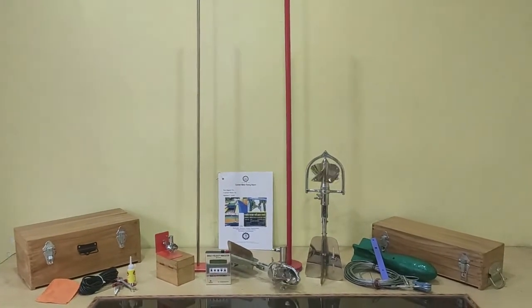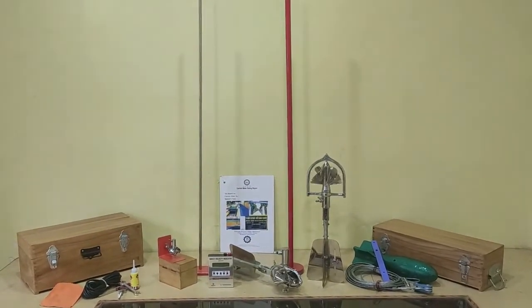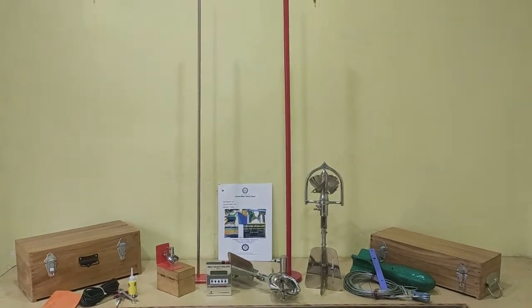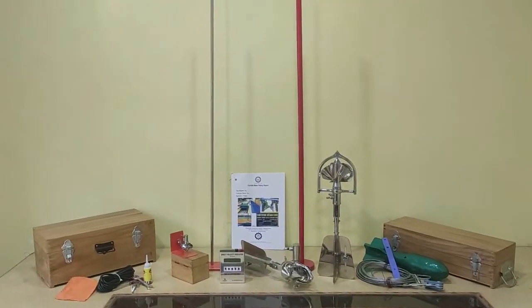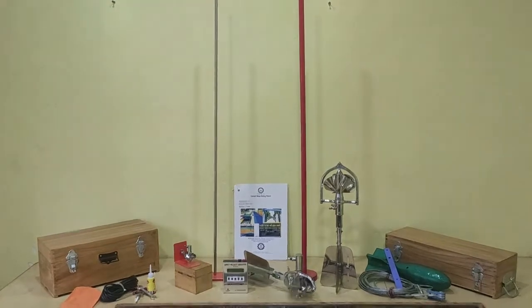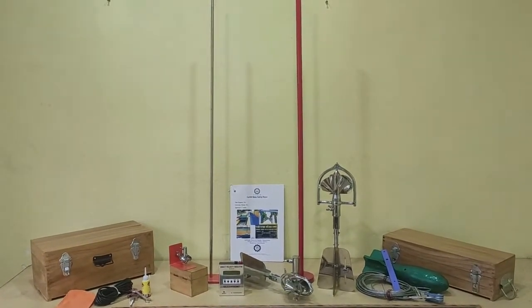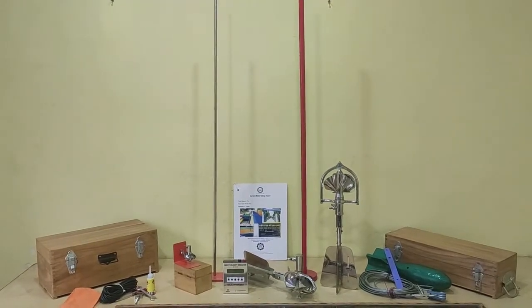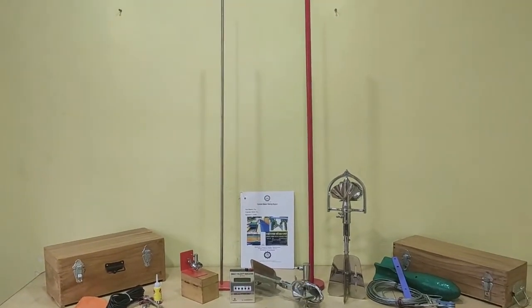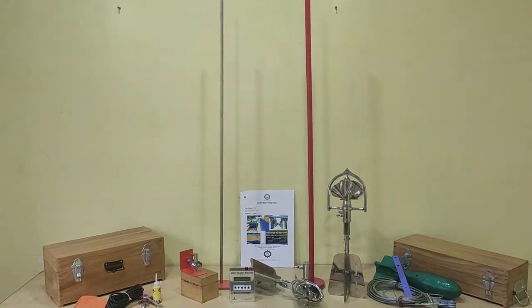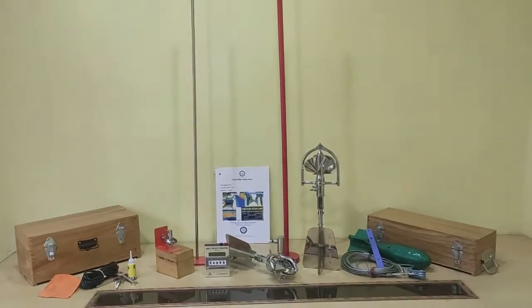There are two types of arrangements we use for taking the velocity with these instruments. First one is the wading rod and the second one is the fish weight. The wading rod we use where the depth of stream is not more than 1 meter, or when the user cannot handle the current meter by the wading rod, then we go for the fish weight arrangement.